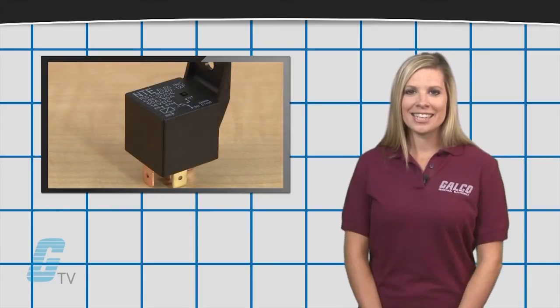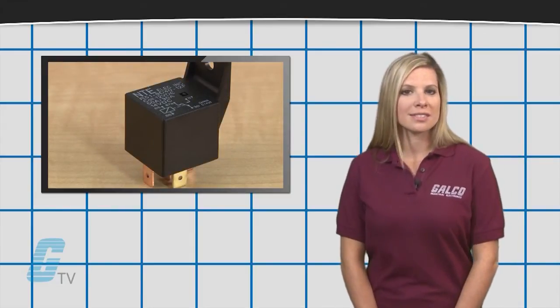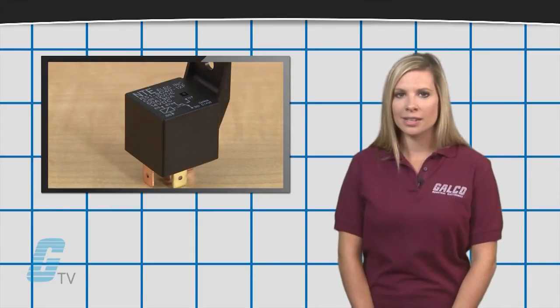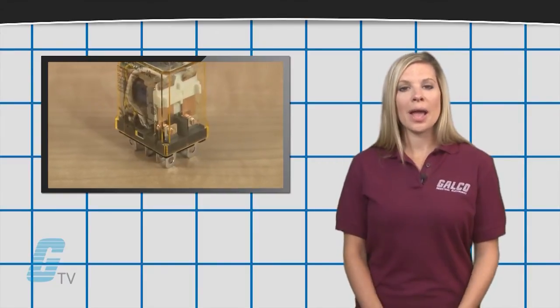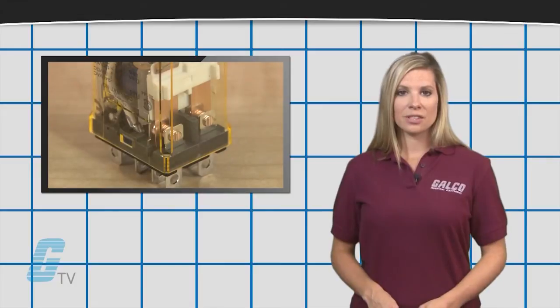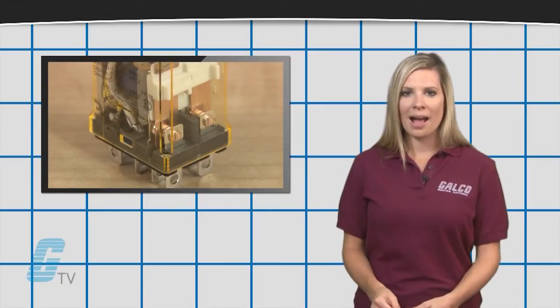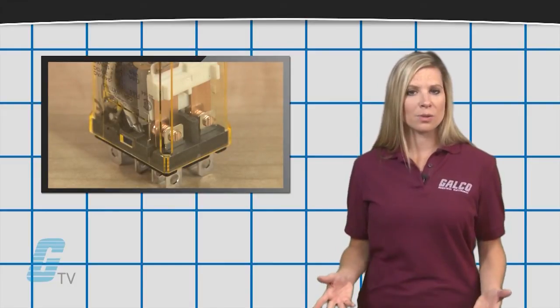The silver tin oxide contacts also offer better resistance to arc erosion and welding, but are also more expensive. For most low and medium power resistive and inductive loads, the silver cadmium oxide contacts are the most widely used.